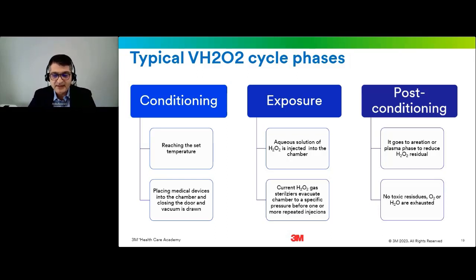During the exposure phase, liquid hydrogen peroxide is vaporized and injected into the chamber, and at this stage, the pressure rises. Depending on the model and the cycle, hydrogen peroxide injection will be in one or multiple injections. In one specific sterilizer, the amount of hydrogen peroxide introduced into the chamber, and thus the duration of the injection, varies depending on the load composition, weight, and temperature. So the amount of the sterilant varies automatically based on the load. And again, different manufacturers have different designs.